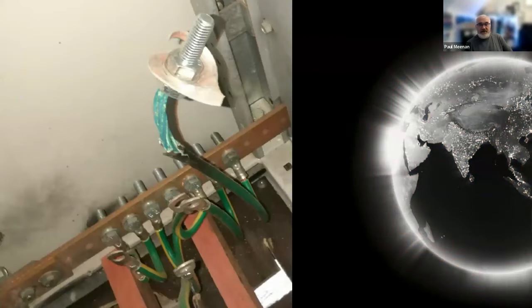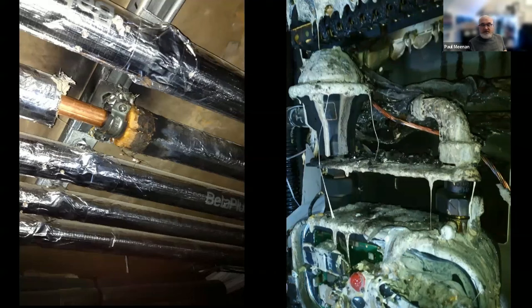One of the other things that you get on earthing is you can get some hazards. So that's a 25 mil conductor that had 198 amps flowing through it. So when it goes wrong, it can go wrong terribly, which is why configuration of your earthing is key. It's very important. If you have access to clamp meters, earth leakage meters, I always recommend, and so does the IET, that before we work on earthing systems, we put a clamp on to see if there's any energy or any charge. There's 134 amps on that one. Not great. And sometimes the effects of having current flowing through the earthing can be quite disastrous.